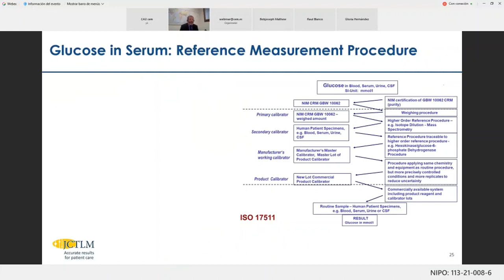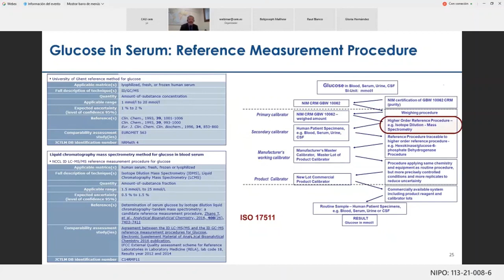The second step in the calibration hierarchy will be the use of those pure materials to develop calibration solutions and use them in mass spectrometric reference methods to measure lower amounts of glucose within serum. And again, if we look into the JCTLM database, we can see a number of reference methods available, developed by different laboratories, which are similar in technique, but slightly different in application. And an important point is to show that those different reference methods are actually comparable.